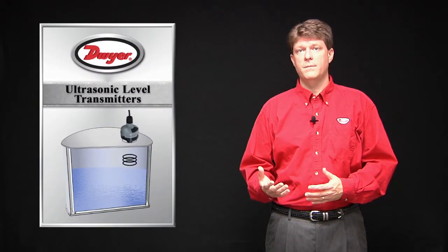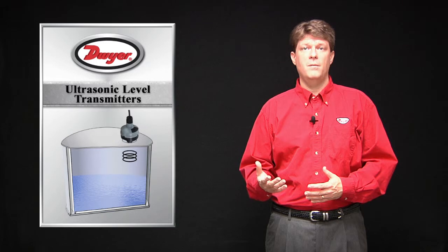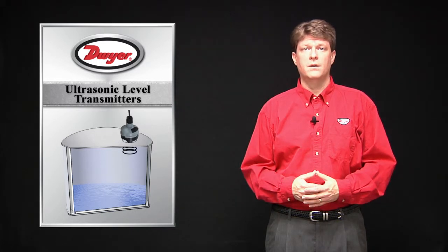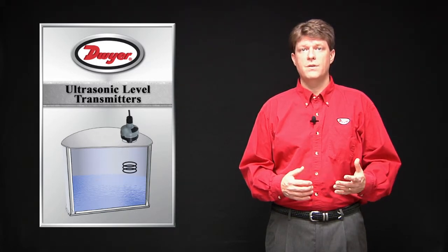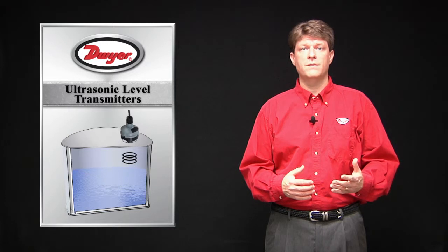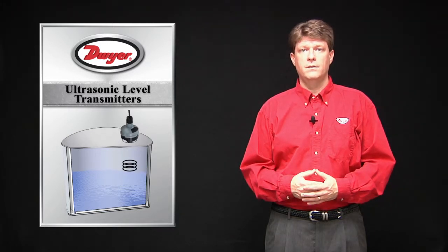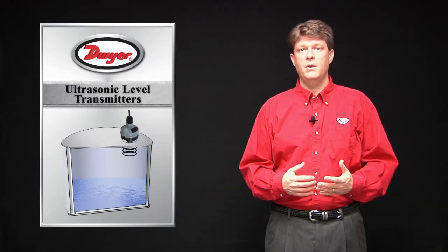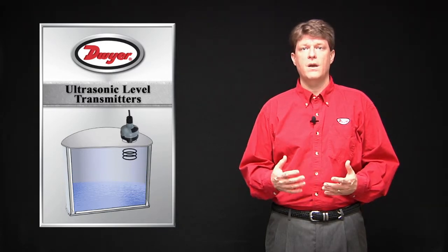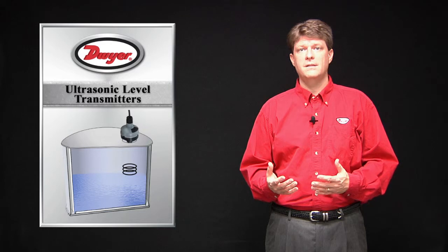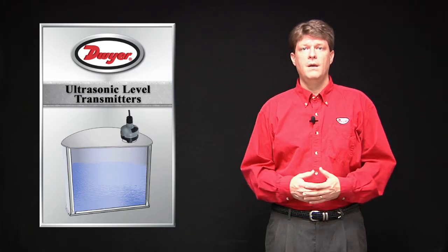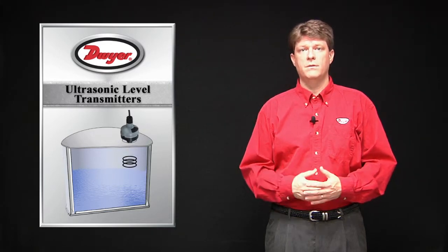Ultrasonic level transmitters emit high frequency sound pulses from the base of the transducer. Each pulse travels through the air, reflects off the liquid surface, and the echo returns back to the transducer where it is received. The sensor measures the time interval from pulse transmission to echo receipt and translates this time into distance or liquid level based on the speed of sound.